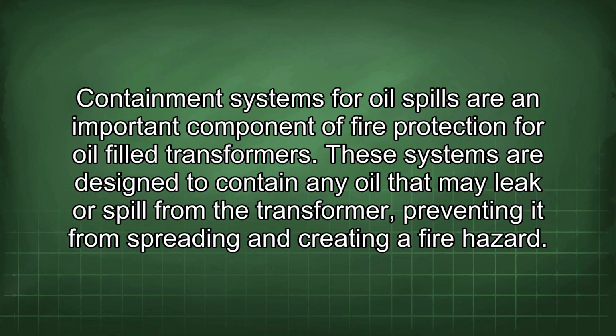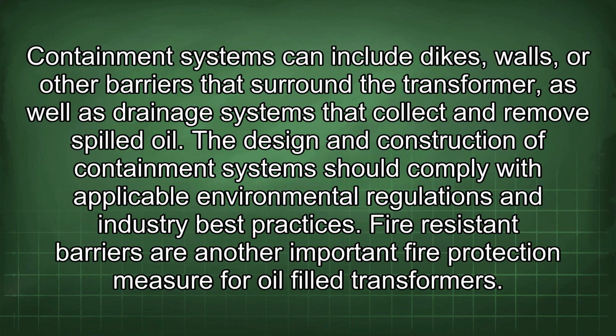Containment systems for oil spills are an important component of fire protection for oil-filled transformers. These systems are designed to contain any oil that may leak or spill from the transformer, preventing it from spreading and creating a fire hazard. Containment systems can include dikes, walls, or other barriers that surround the transformer, as well as drainage systems that collect and remove spilled oil. The design and construction of containment systems should comply with applicable environmental regulations and industry best practices.